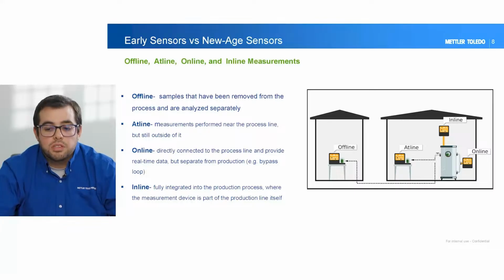One of Pendotech's first innovations was our inline single-use pressure sensor. These sensors, which are now a key component in many bioprocesses, enabled highly accurate, real-time pressure measurements at a time when most pressure measurements were made with reusable stainless steel pressure gauges. This approach had contamination risks and required operators to manually record the pressure value.